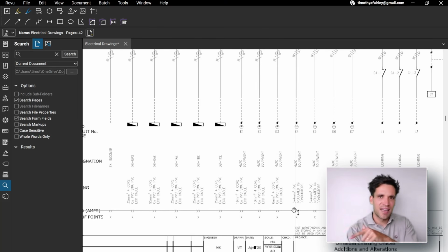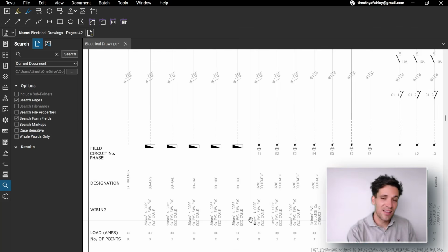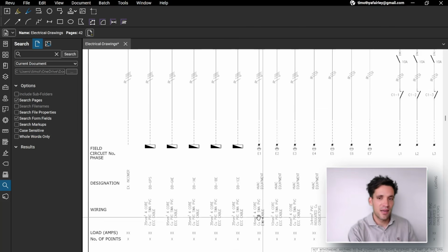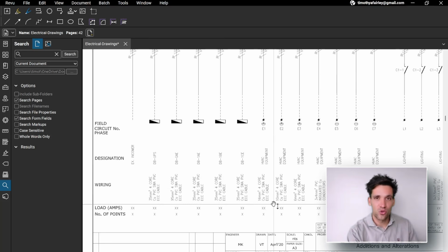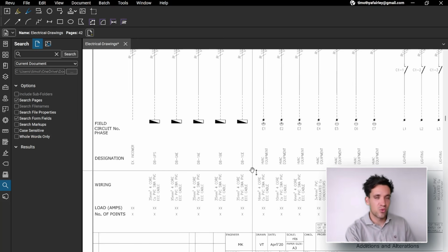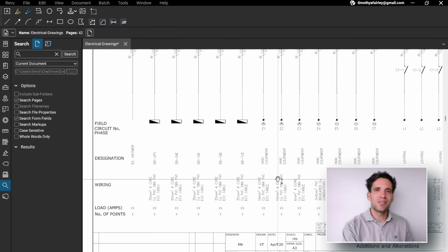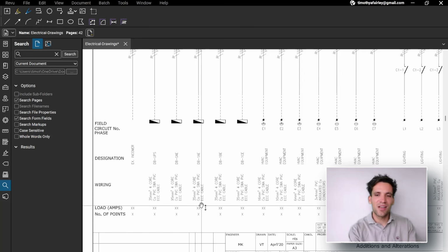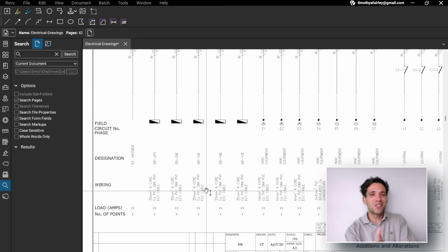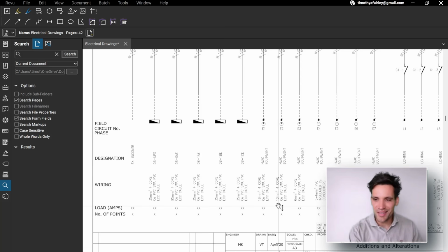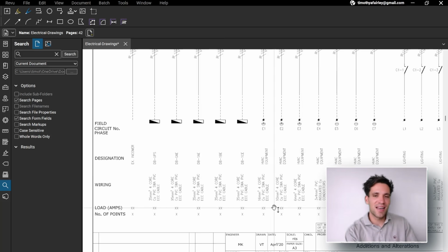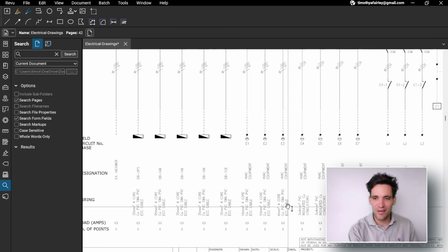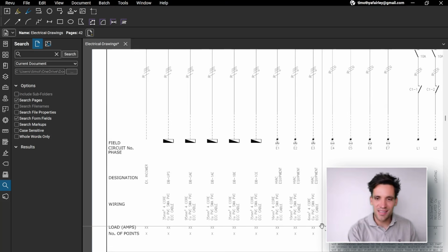Sometimes they don't list the cables on the actual drawings. Other times they do, but sometimes they'll give you a cable schedule that accompanies the drawings, which is more useful because it tells you the lengths of all the cables. Now, weirdly, I've seen a couple of design packages where on the cable schedule, they don't nominate the length of the cable, which to me doesn't make any sense, because for them to size the cable, to work out whether that has to be a 35mm or a 50mm cable, you need to know the length. So the lengths must exist. To size it in any sort of design software, you need to know the length of the cable. So the lengths will exist somewhere.